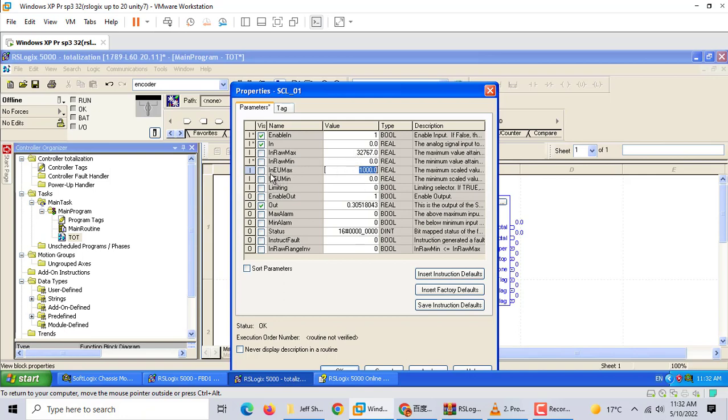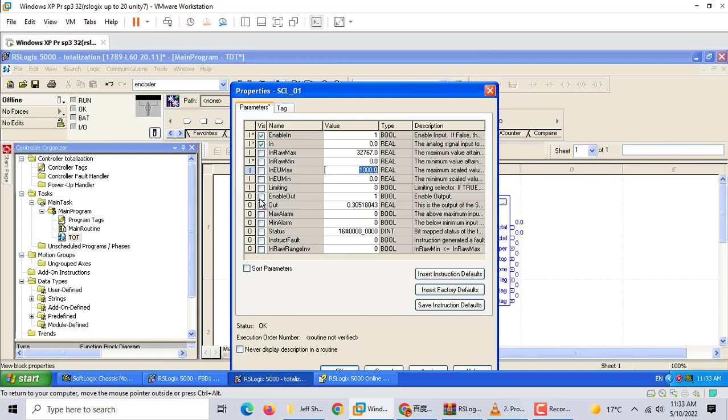Now we can add the totalizer. We configure this with input minimum zero and input raw maximum 32767. Which number you use should follow your input module analog manual. You can find what number you should use there.